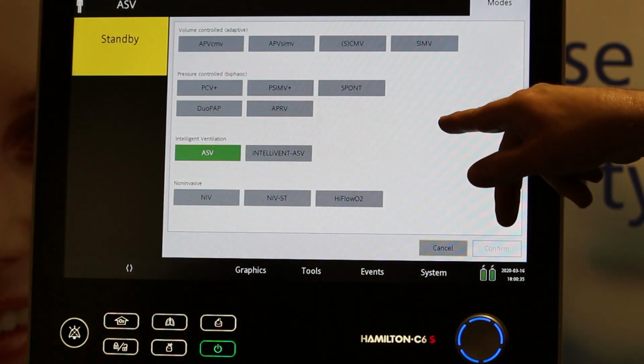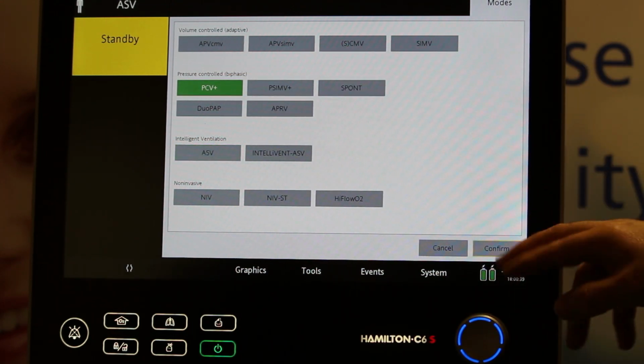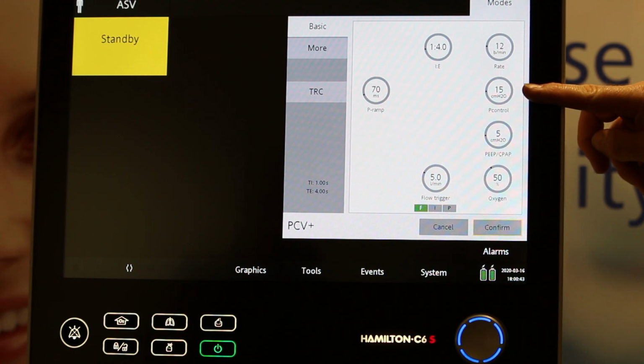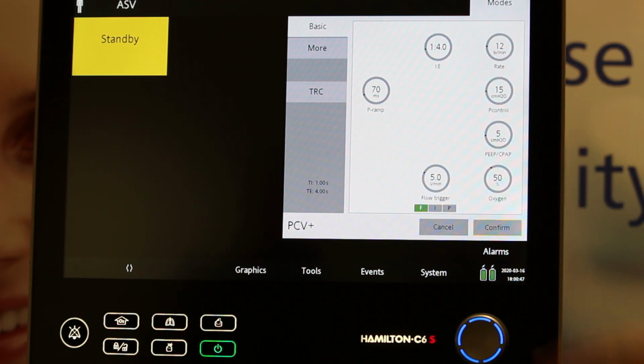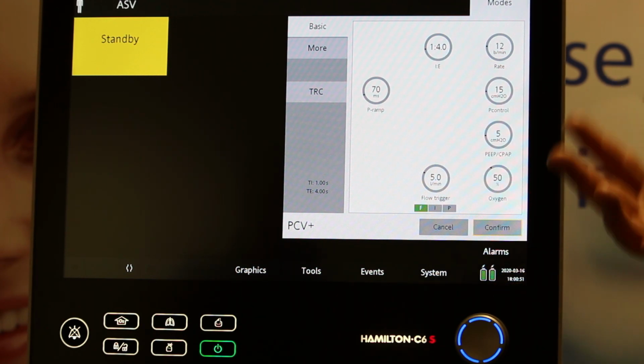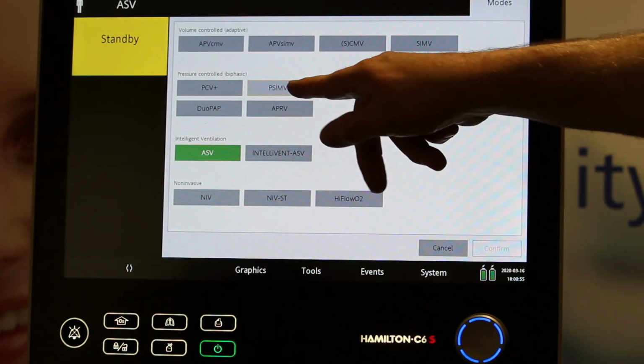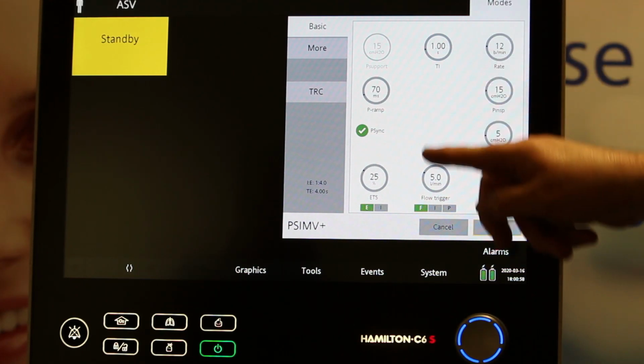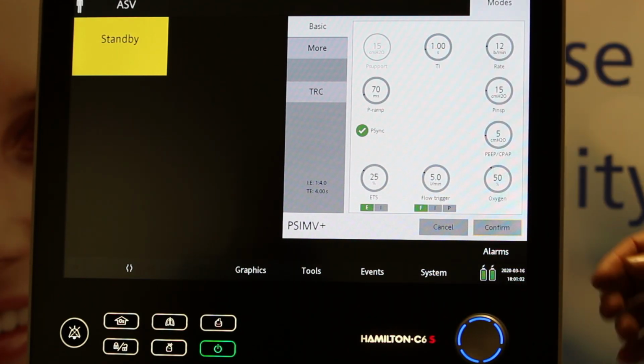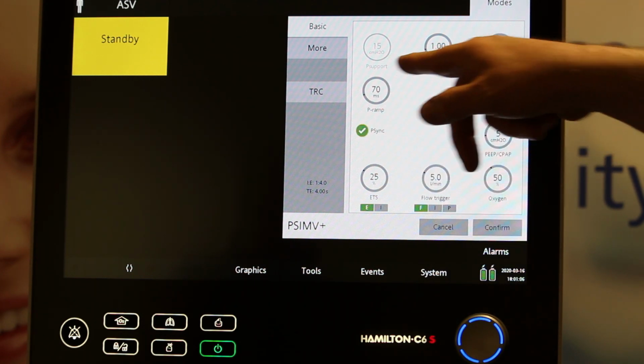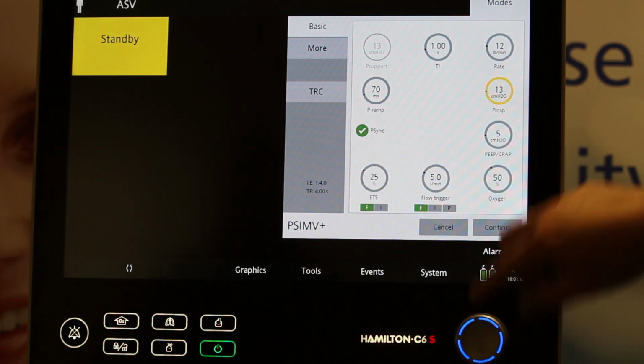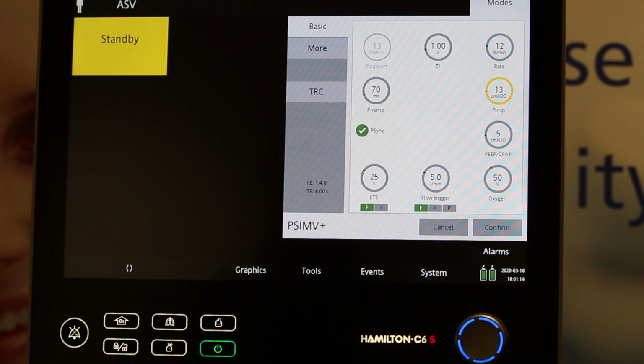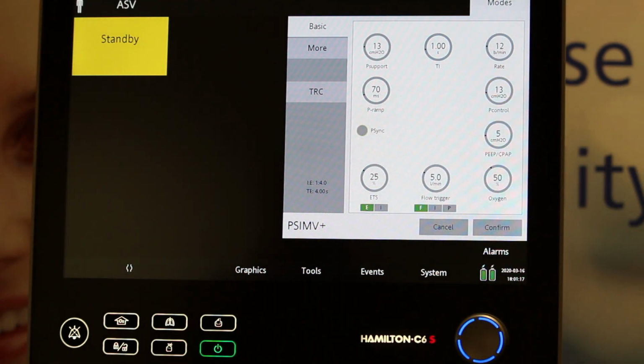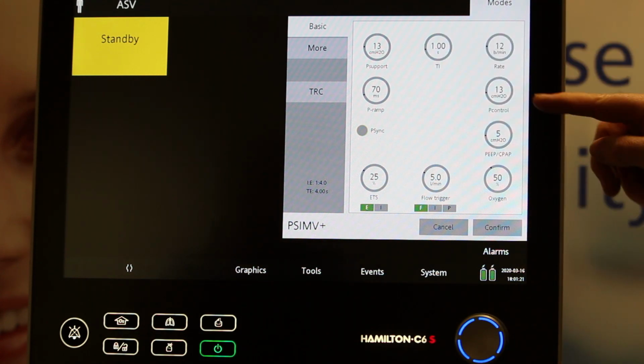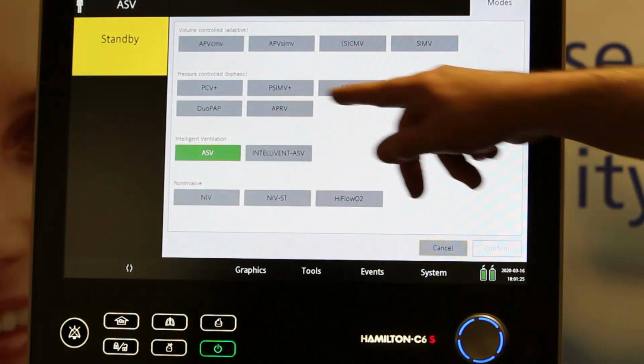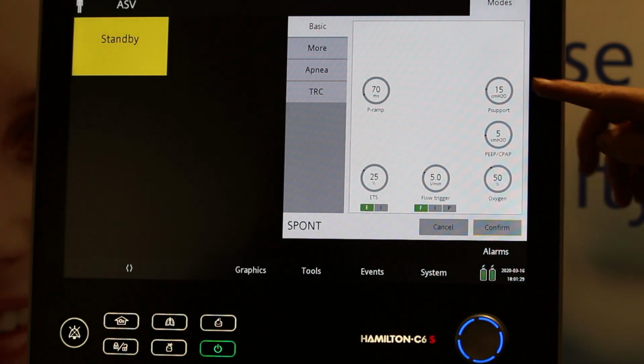So that is SIMV. Moving down to the pressure controlled biphasic modes, PCV, pressure controlled ventilation. You're setting your rate, also your pressure control over your PEEP, oxygen, IE ratio, trigger, and P-ramp. Again, there's no support in this mode, so the ventilator is not expecting any interaction from the patient. Then pressure SIMV, all of the same settings, but there is pressure support in the mode, so it'll synchronize with patient activity. Hamilton have something called P-sync, so that is syncing the support to your inspiration pressure. So automatically, if I turn my inspiration pressure to 13, my support automatically goes to 13. If you want to have clinically different support to your inspiration pressure, just untick your P-sync, and that then activates pressure support if you want to adjust that to have it differently to your pressure control, your inspiratory pressure. Pressure SIMV. Then SPONT is just your pressure support, or CPAP, you're just setting your support over your PEEP.